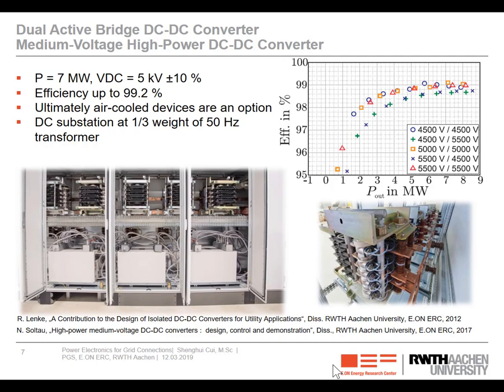And if we operate the transformer at 1 kilohertz, compared to the 50 hertz line frequency transformer, the size and weight are decreased to 1/10, so 10% of the line frequency transformer. And if you calculate the weight of the total DC substation, not only the transformers, but also all the converters, cooling systems and switchgear, the total weight is still only 1/3 of the line frequency transformer. So it presents very high power density.